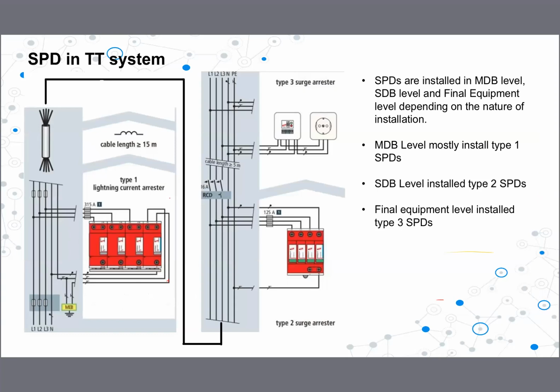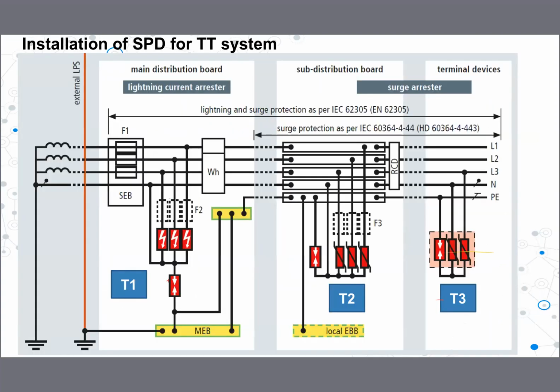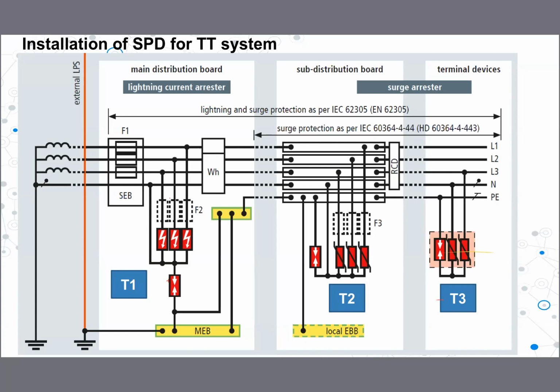This is the correct way of installing SPDs in the TT system. Now in the TT system, here you can see we install type 1 at the entry point, then type 2 at the SDB level, and type 3 at the terminal level, right? All three levels we can install SPDs as shown in the diagram, right? Then again, to elaborate further, at the entry point, type 1, this is how we install it, every phase, then neutral and earth, right? Then type 2 and type 3, right? Type 1 looks after lightning impulse. Type 2 and 3 look after switching surges, indirect voltage surges, right?